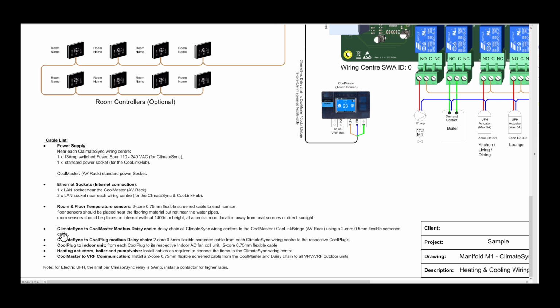The Modbus daisy chain, as we said, between the ClimateSyncs to the CoolMaster will be a 0.5 millimeter flexible screened cable. The ClimateSync to CoolPlugs, as we said, it's the same type of cable that goes to all the CoolPlugs if the CoolPlugs are by the indoor units. Between the CoolPlug and the indoor unit, it will normally be a 2-core 0.75 millimeter flexible cable. On Fujitsu old systems, that will be a 3-core. Midea, it may be a 3-core, so have a look at the specific wiring diagram for that specific indoor unit.